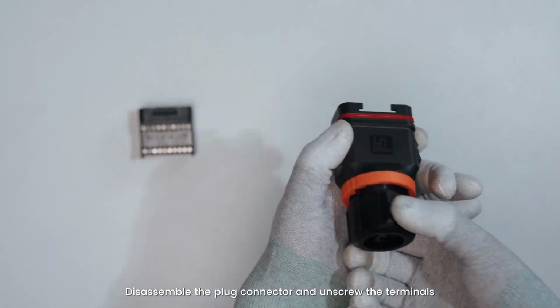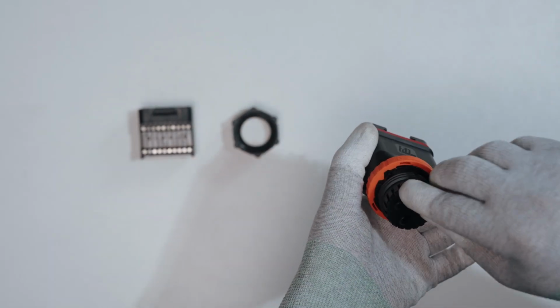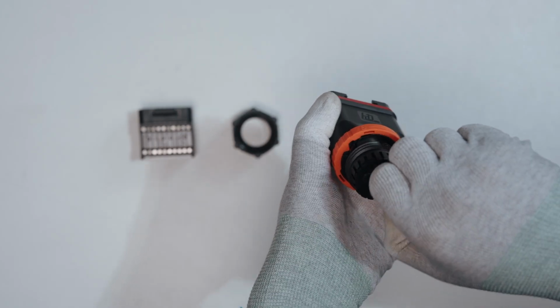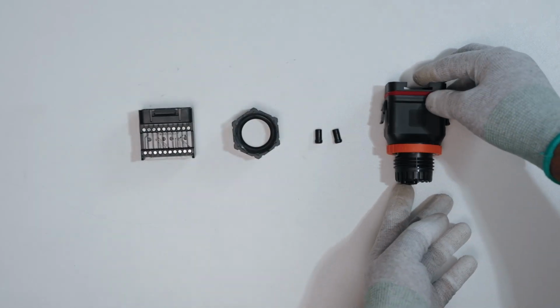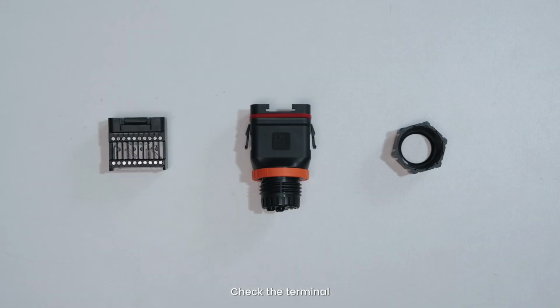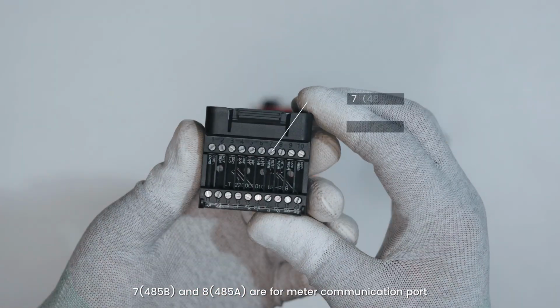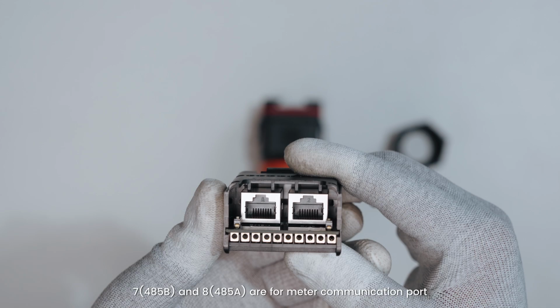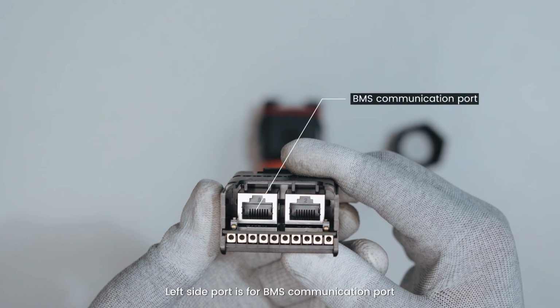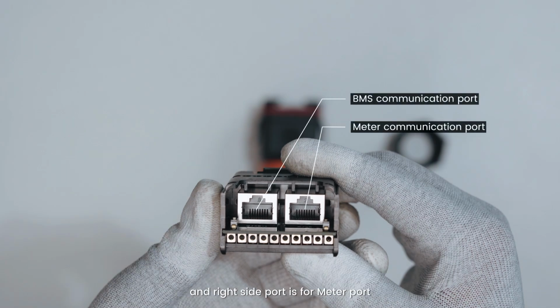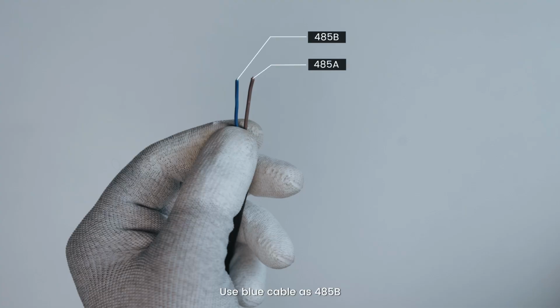Disassemble the plug connector and unscrew the terminals. Check the terminal. 7 (485B) and 8 (485A) are for meter communication port. Left side port is for BMS communication port and right side port is for meter port. It can also communicate with meter. Use blue cable as 485B, brown cable as 485A.